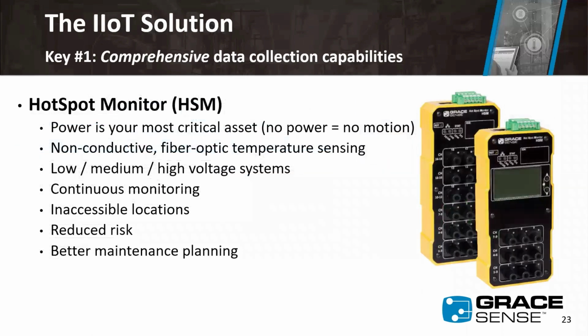The second way we develop comprehensive data collection capabilities is by developing targeted technologies for specific applications. This hotspot monitor is designed for medium voltage issues where you're looking for hotspots, typically in bus bar, and it can be squirreled away as a good replacement for thermographic inspection. We have a fiber optic temperature sensor that runs into either our 9-channel or 18-channel devices, allowing non-conductive monitoring of hotspots in high voltage, high current applications without noise interference from the thing being monitored. These are also connectable to the IoT system directly, or you can bring data straight into your PLC over Modbus TCP IP or Ethernet IP.